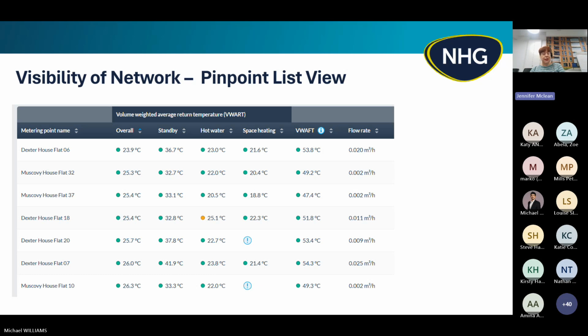Of course, prior to the HNES works, we had very limited visibility of the network, and certainly we didn't have any visibility of how the individual HIUs were operating and their performance indicators. Now we have a really good level of insight into how the HIUs are functioning and the average return temperatures that are going through them. So this is an example of the data that we get from the Guru Hub via the Pinpoint portal. It gives us an indication, through a traffic light system, of which sites and which HIUs are performing really well. Where you can see the green indicators, that shows the HIUs are working well, and the flow rates are also within acceptable parameters.